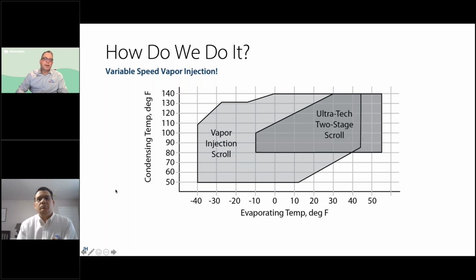It'll increase, decrease RPM. When we get cold enough, then it needs, and this sounds counterintuitive, to cool the compressor. It's designed for high condensing temperatures and low evaporating temperatures. So what that means is it's cold outside and we're heating domestic hot water, for example. Maybe we're running at 135 degree supply temperature. So it is actually cooling the compressor in those conditions. What happens is it turns on that vapor injection as it needs it for capacity, or it'll turn it off if it's needing a little bit less capacity at those milder temperatures. So having vapor injection helps that compressor operate at much colder temperatures. It increases our efficiencies at those cold temperatures, and we can still operate as just a normal scroll when it's not turned on and have the ability to increase RPMs based upon the load. Next slide.